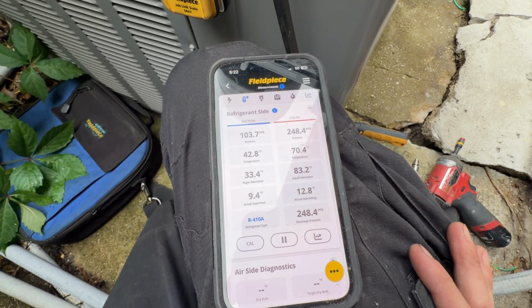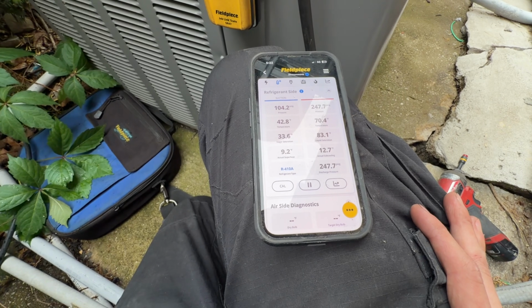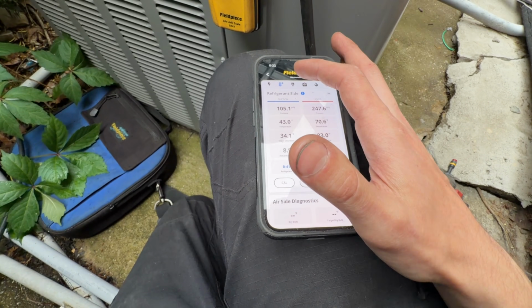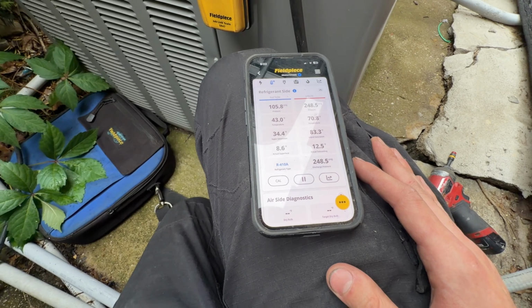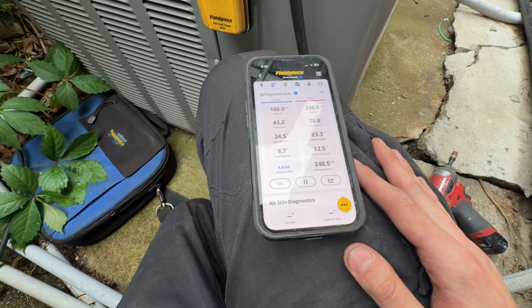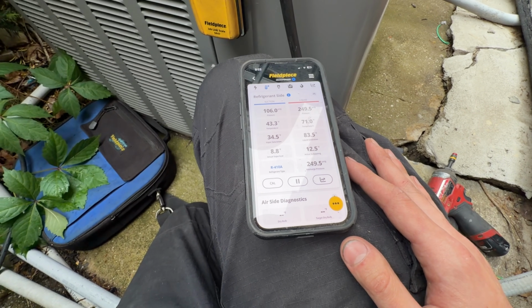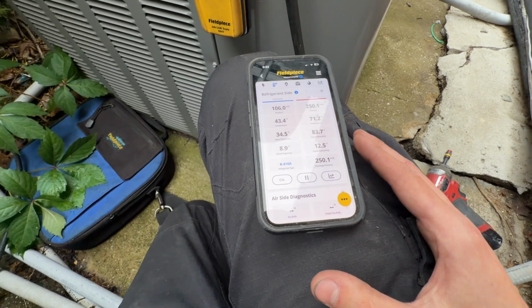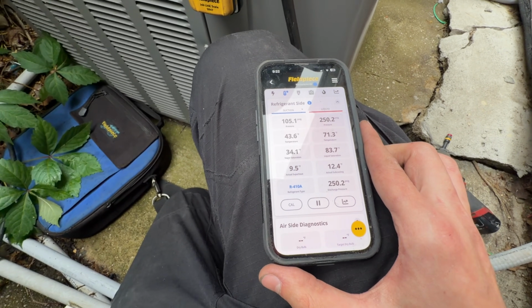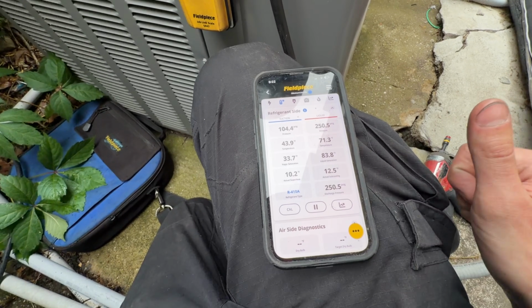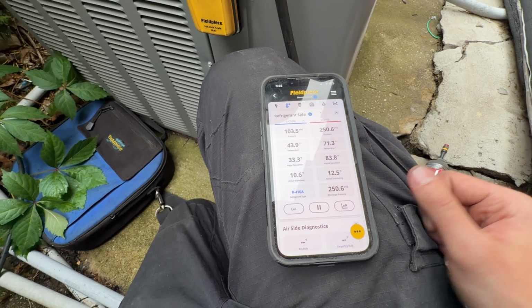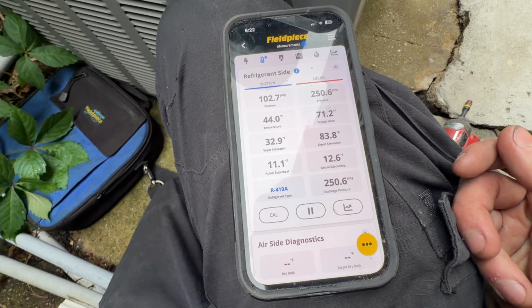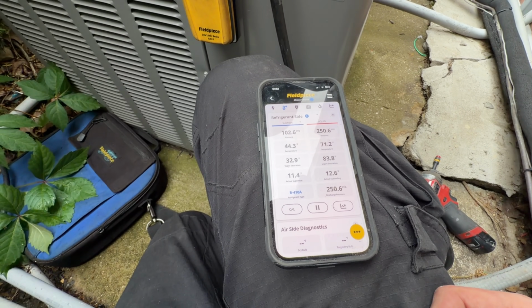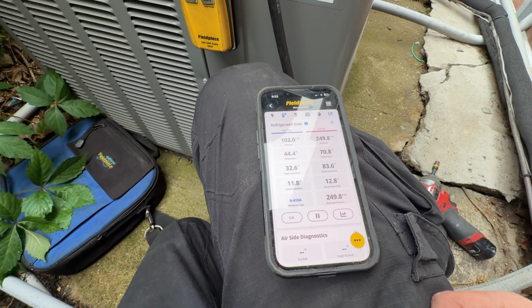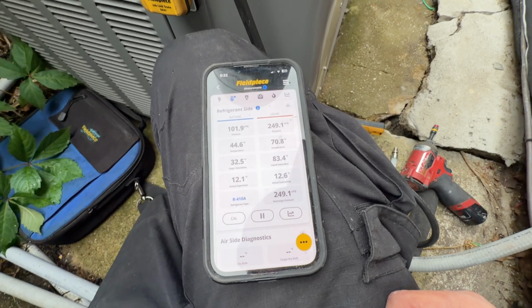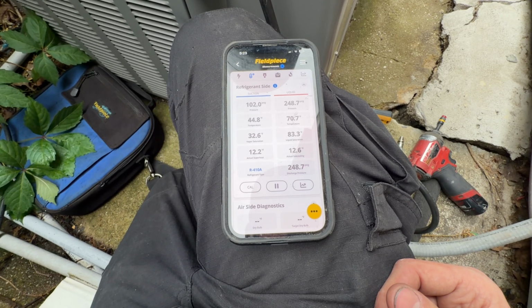So 12 degrees of subcooling. It's about 10 degrees of superheat. I am happy with these numbers. It's pretty much exactly where I would like them to be. It'd be nice if the vapor saturation was up a little more, but considering the temperature, it makes sense that it would be lower. So the system's cooling, and I'll go inside with my psychrometers and I'll show you the delta T that we got.